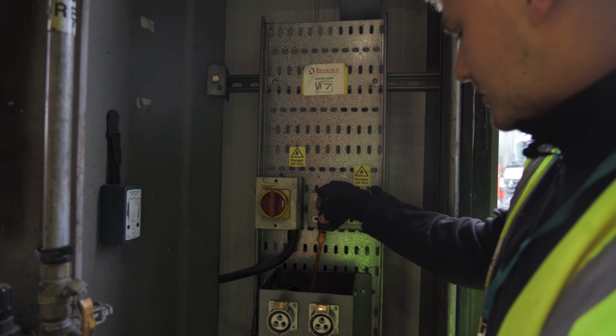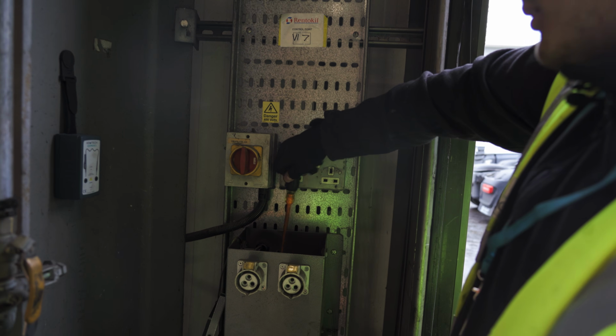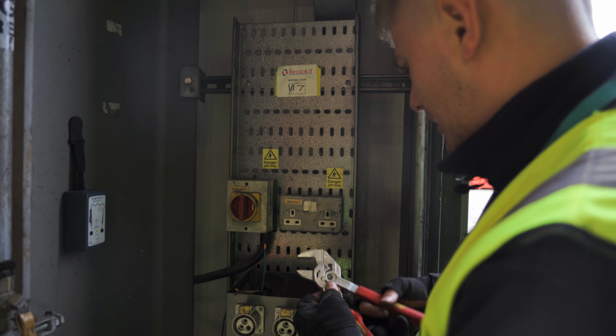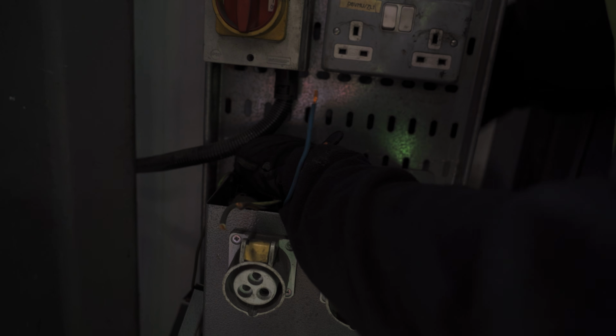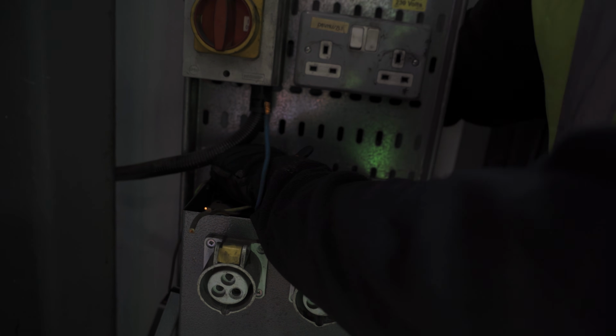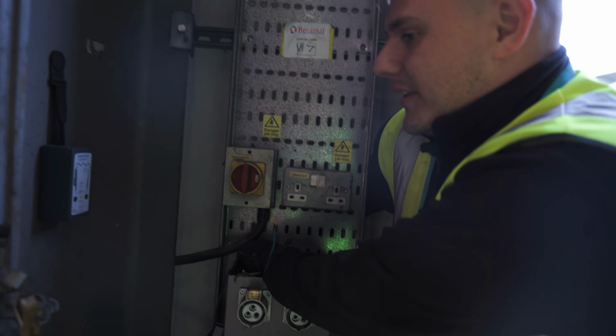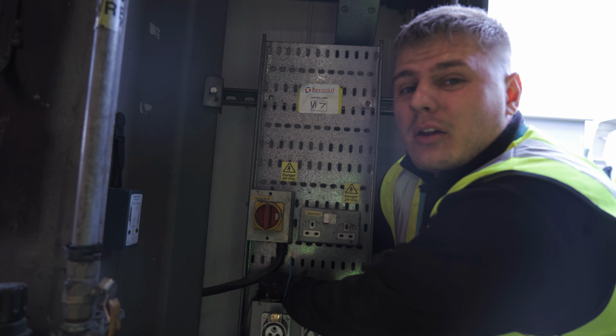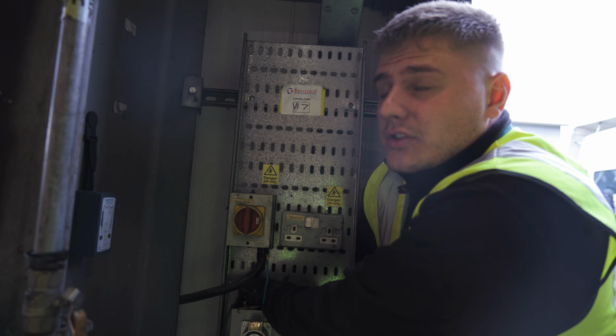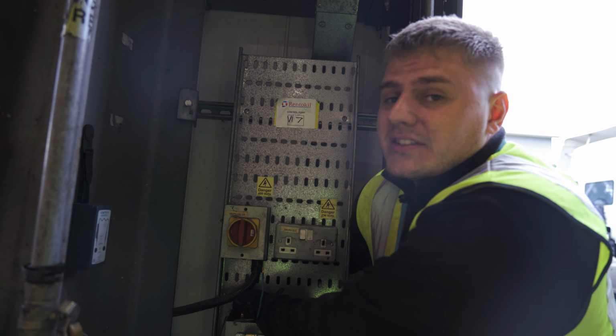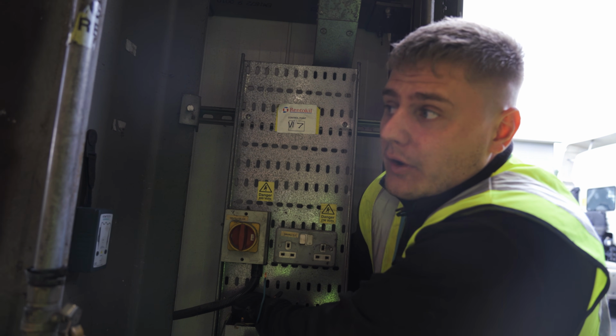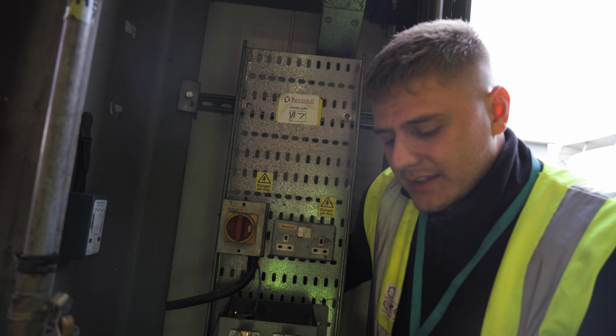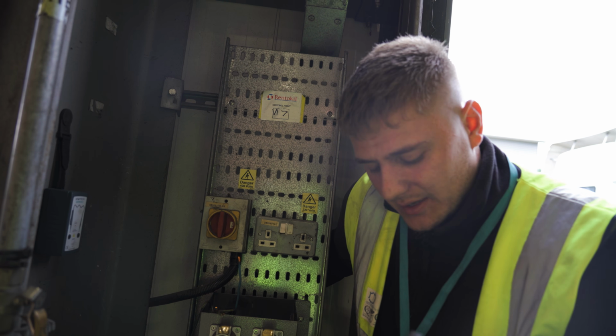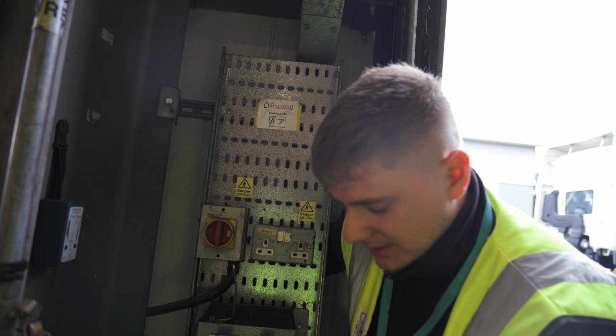Just disconnect these - so this is the end of a 4mm radial. Get the Copex loosened off. I'm just spinning basically the back of the Copex gland, holding onto the lock ring, and that's allowing me to spin the lock ring off, because transformers get very warm. This is nice and toasty in here even now, even though it's been turned off 5 minutes, so this plastic is obviously expanding and going brittle basically.